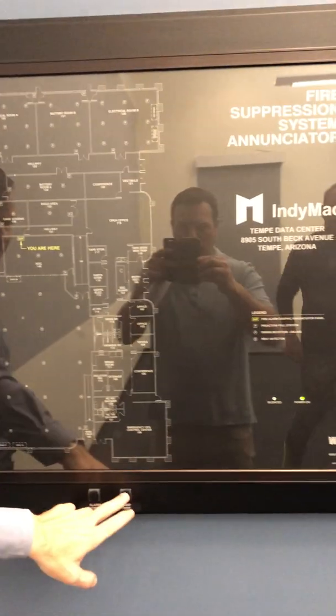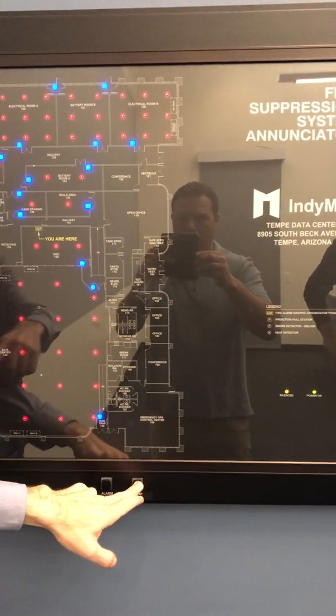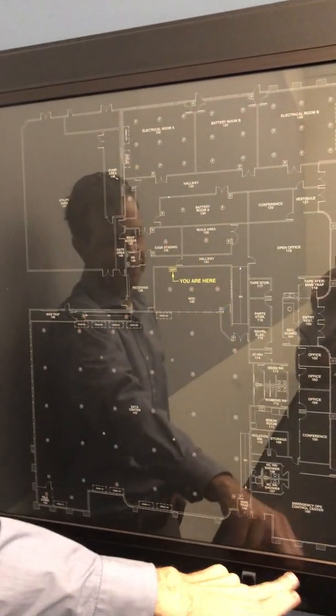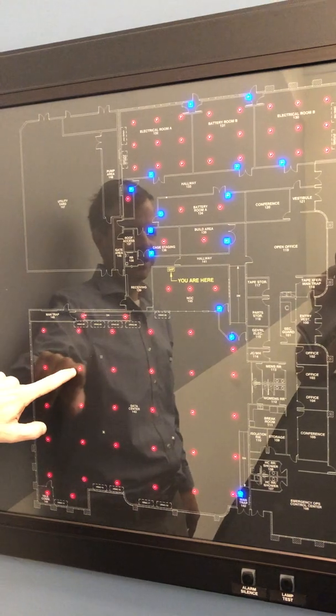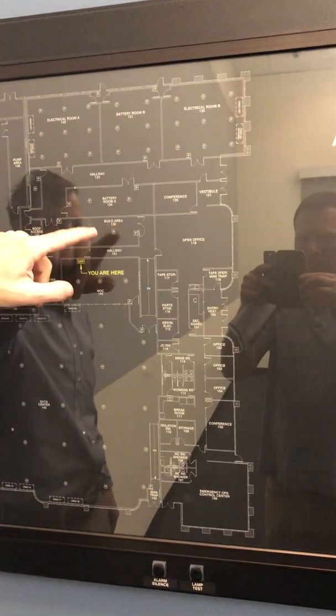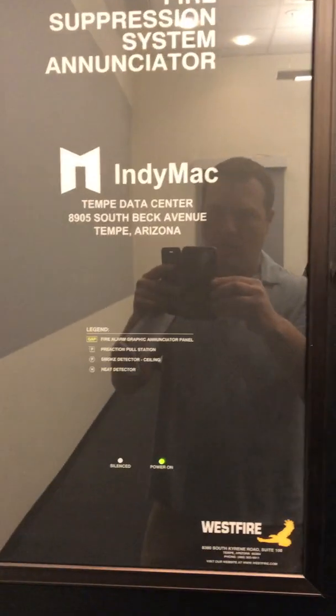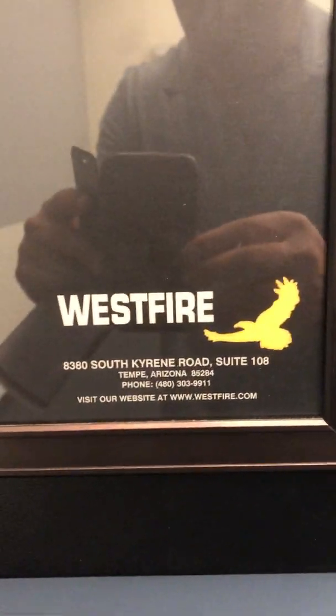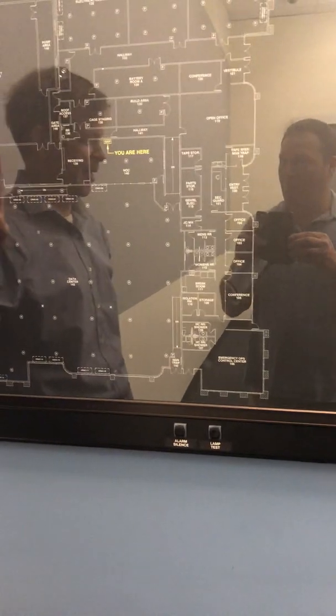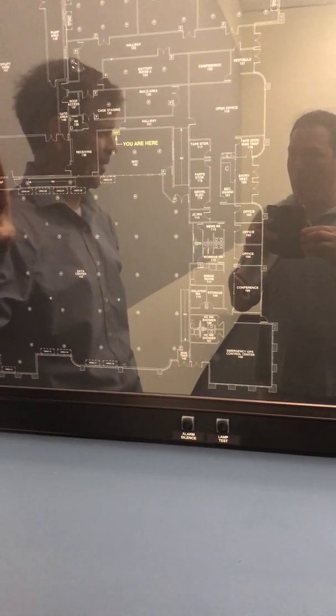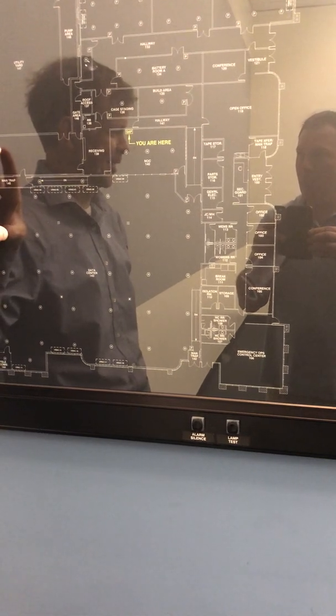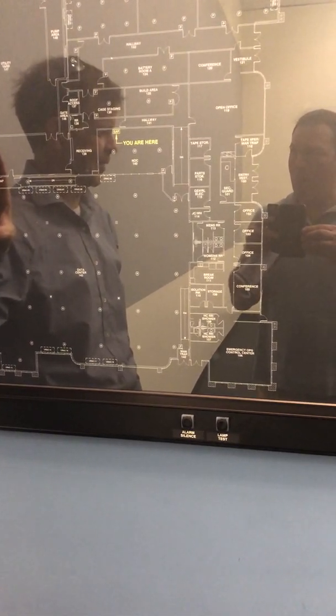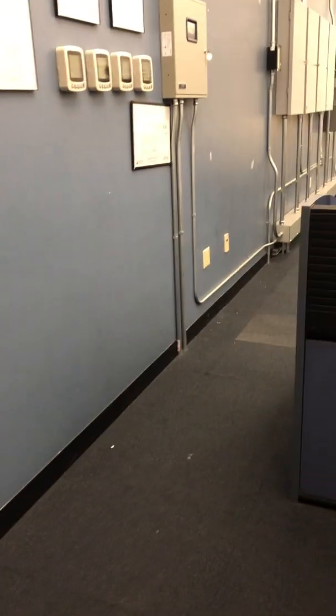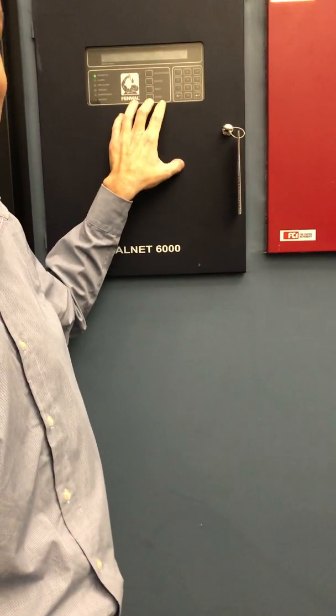So on the fire annunciator board, the addressable devices will light up, which will allow the precise location of if a heat detector is going off, if a pull station is going off in any of the pre-action spaces, as it's a more advanced system. So the software that is built into this is proprietary under license, but Westfire, the vendor, has my authorization to transfer the bank's special written software over when the new site occupant comes in. Thank you. So this handles the pre-action sections of the building.